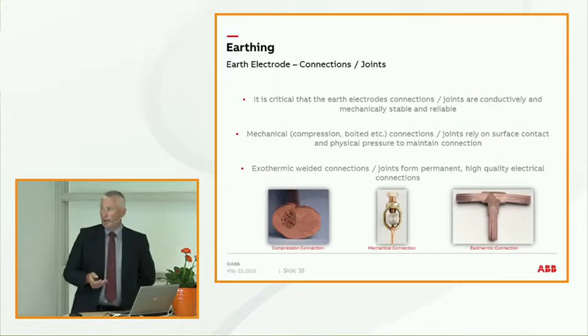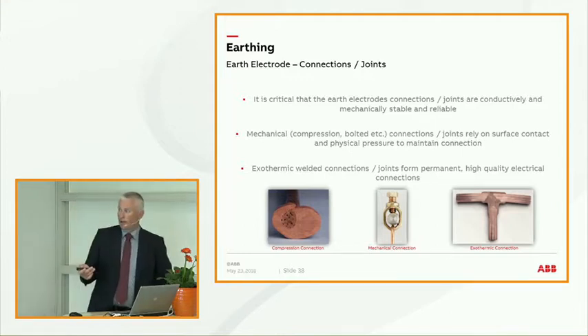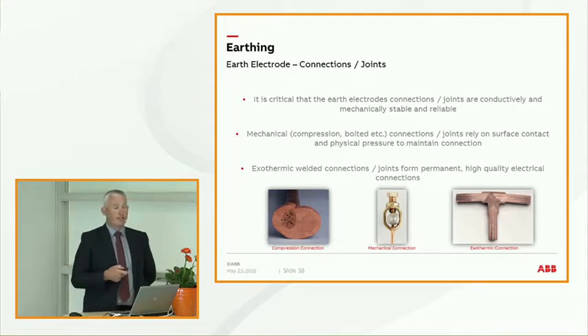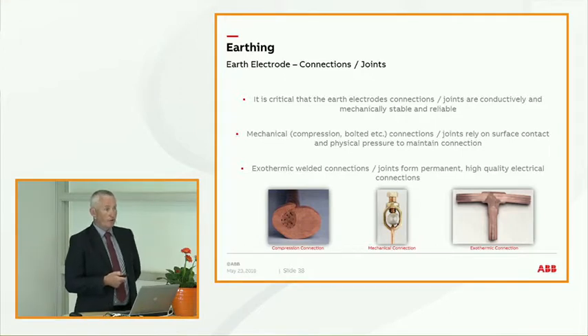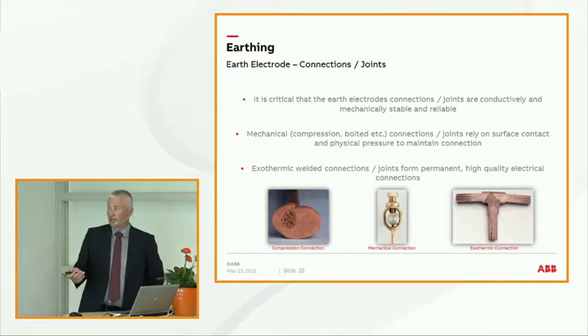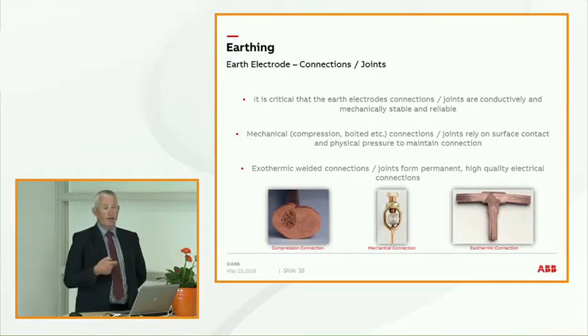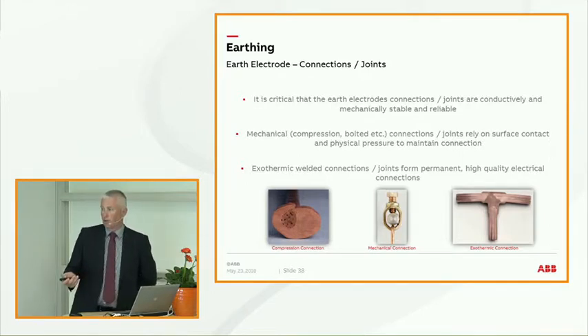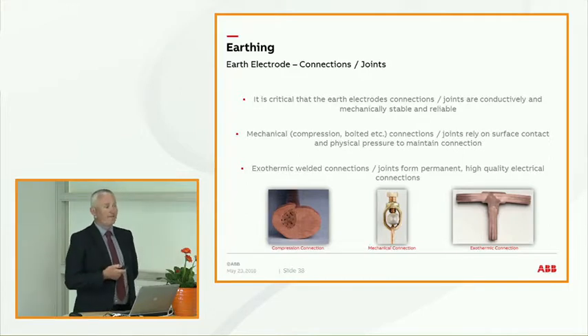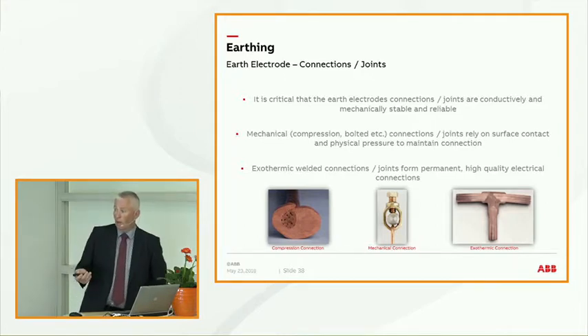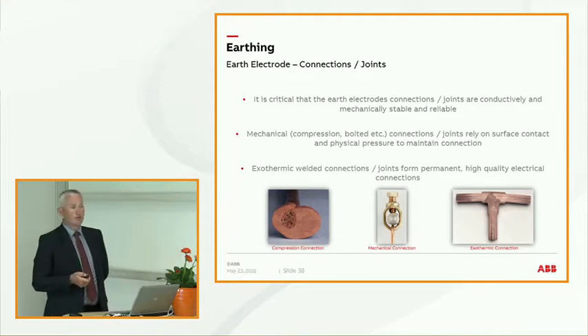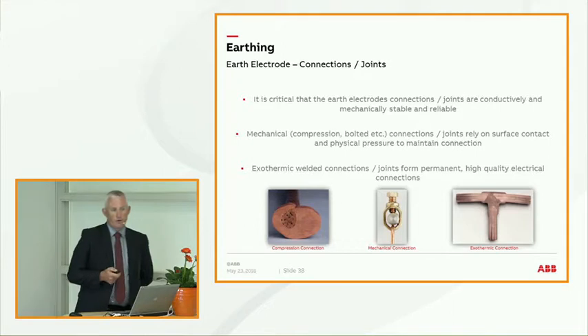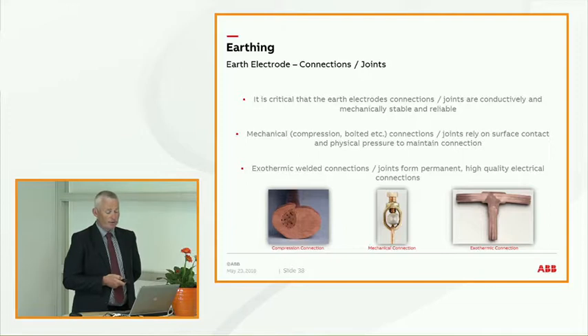The different joints. In the UK, for instance, and the Middle East, the exothermic welded joint is specified by the majority of utility companies because it basically lasts, it doesn't corrode, and it's got better current carrying expectations. The mechanical connections can fail over a period of time. Once you get moisture in those joints, they can fail in an earthing application. And then we've got the compression joints. The tools do bring those together, but you've not got rid of the ingress of water. It's just showing some of the different connection types for all the earthing systems.